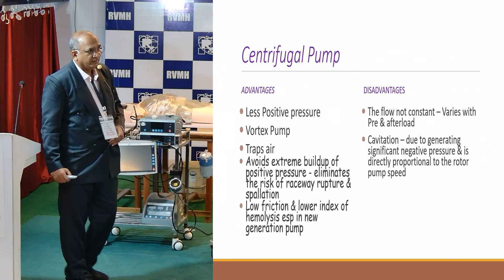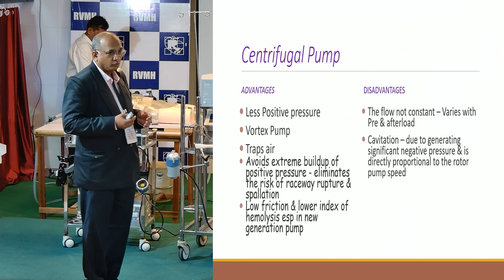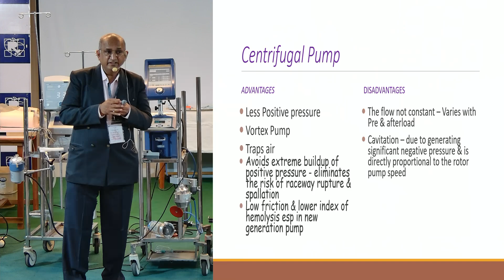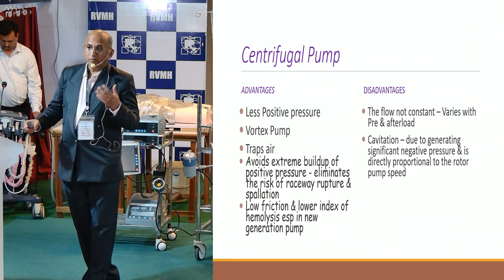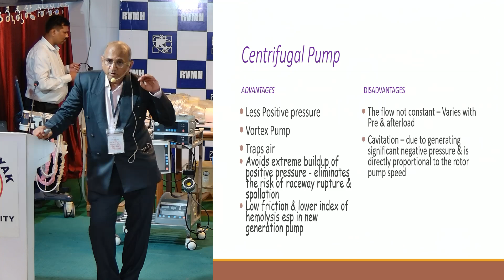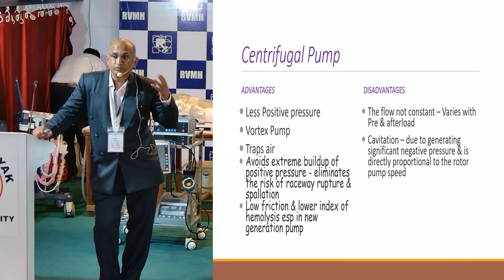The disadvantage is the flow is not constant because it depends on the preload and afterload, and it can create cavitation. What will happen is, suppose your preload is decreased. The pump is moving, so it will create more and more vacuum. Because there is a lot of vacuum and suction effect, there's cavitation in the fluid: air is released in the blood itself, and you have air coming in the circuit. That is what we call cavitation, and that usually occurs when your negative pressure goes more than 200. If the negative pressure is more than 200 or 250, you will see the cavitation and you will see the air in the circuit.